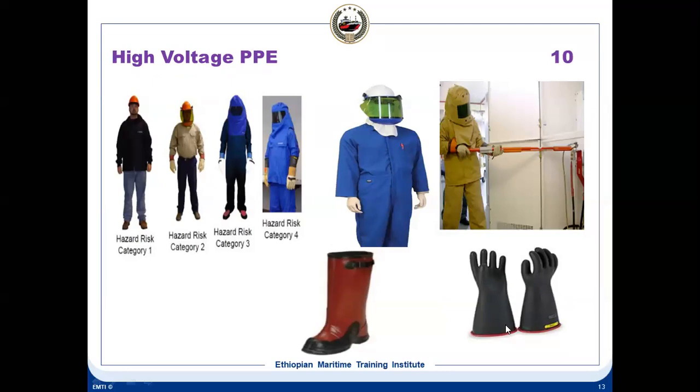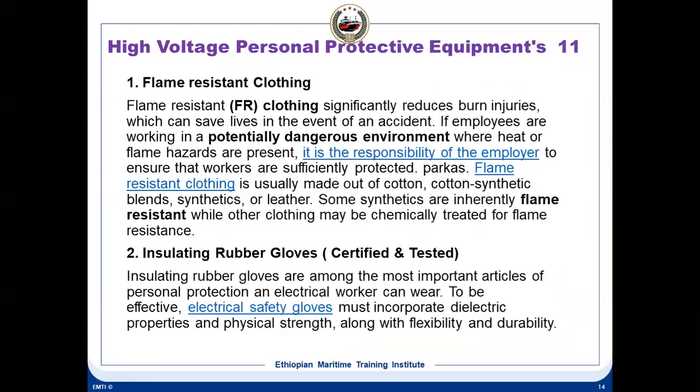It's safe to use, because especially when you touch the bus bar or when you touch the starter part inside and all this breaker and all, you have to wear this. Always you have to wear the hand gloves, high voltage hand gloves. And you have to make sure that there is no crack or no hole, nothing else, and it should be certified. It should be tested also. These are the mandatory requirements of this.